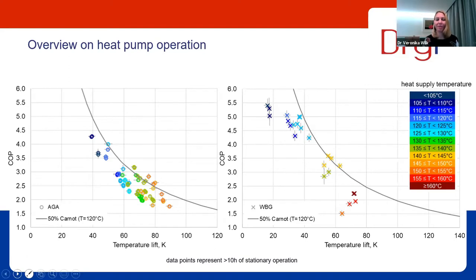So we have here summarized 8,000 hours of operation in these two diagrams. And we have done this by representing a stationary operation that lasts for at least 10 hours by a single data point. So all these different conditions are summarized in different data points that represent this type of stationary operation. And stationary operation is characterized by the same inlet and outlet conditions of the heat pump and the same settings on the compressor. You also see error bars, more prominent for the Wienerberger installation. This is the variation that you find in the data when summarizing it as a single data point. So this is a very good way to get an overview on the whole operation.